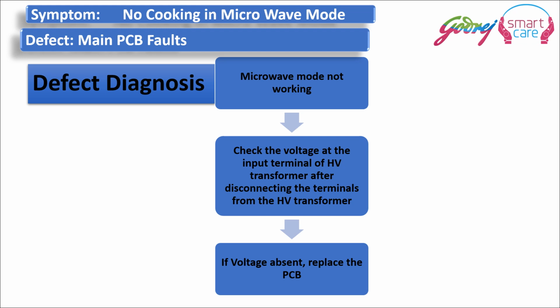The next diagnosis is of main PCB fault. How can we check it? The defect is that microwave mode is not working. We can check the voltage at the input terminal of the transformer after disconnecting the terminals from the HV transformer. You have to remember that we should not check the high voltage circuit when the circuit is on, or when the voltage is supplied to the circuit.